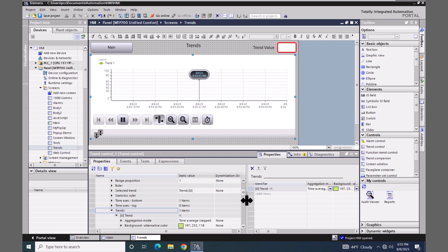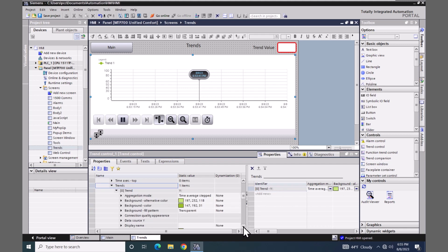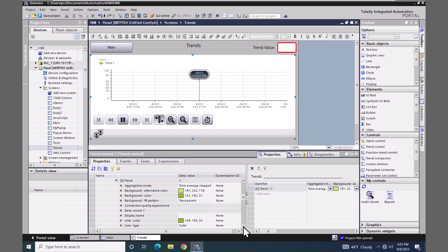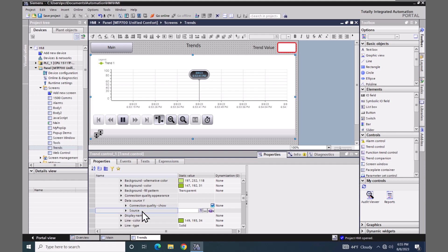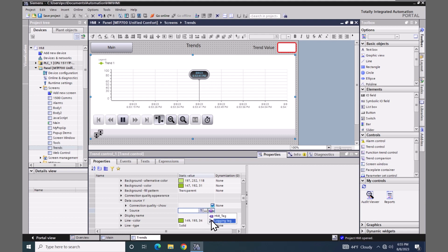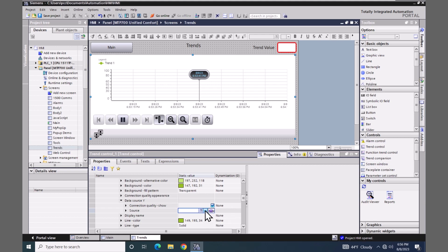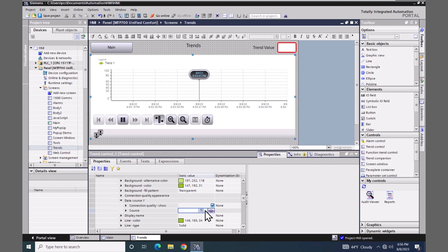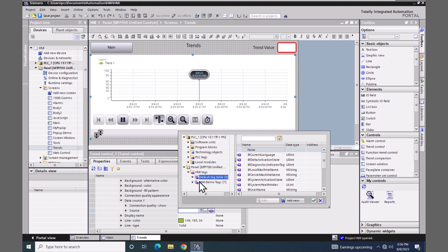If I want to add additional trend pens I can add those in here. I can just configure the existing trend pen. We're just going to do one trend value. Scroll the trend properties down and look at the data source y first and then the source configuration. This button here allows you to pick the type of trend. If I pick HMI tag it will be real-time. If I select logging tag it will be historical. We are going to do real-time trending first so I will select HMI tag. Then I will browse for the tag that I want to display. So I will select my HMI demo tags table and select the int tag 1. The update rate is going to be based on the acquisition rate of the actual tag.